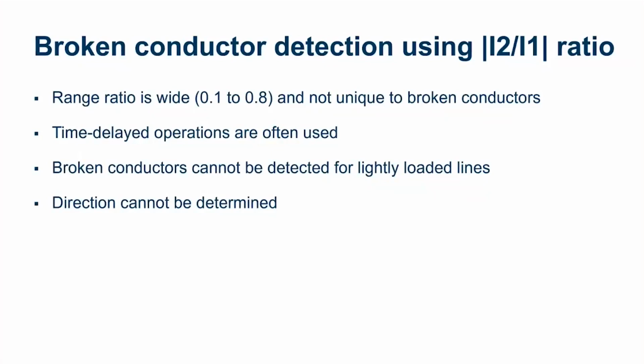Another issue is broken conductors cannot be detected for really lightly loaded lines. What can happen is, if the charging current is comparable to the load current, when the conductor breaks, the phase that has seen the broken conductor is not going to see a large change in current. So we're not going to see much I2 to I1, and we're not going to be able to detect it.